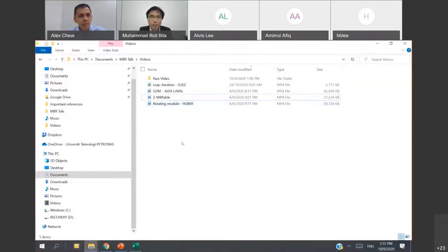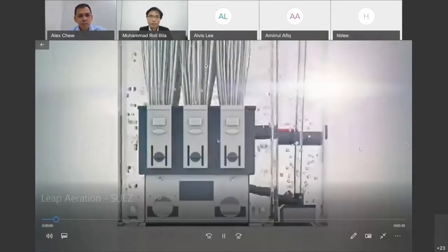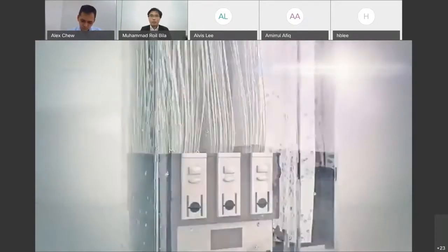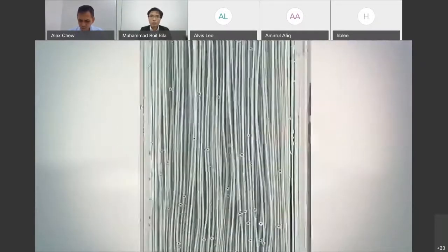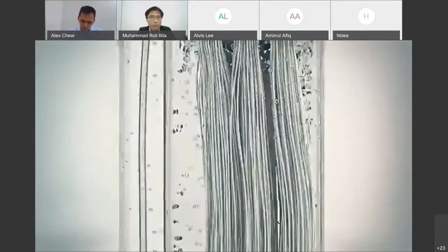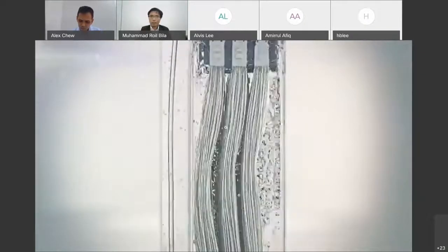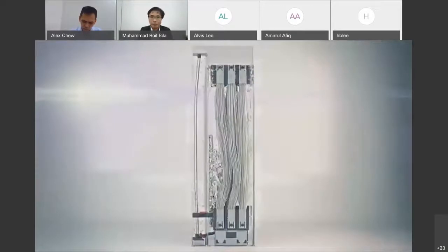For example, the first one is called LEAP MBR. This technology is commercialized by Suez. They use what they call slug flow to enhance the cleaning of the membrane. As such, it reduces the energy consumption significantly. So you see here that the air bubbles go intermittently with a high flow, and then the membrane can sway to the left and right, vibrating along the process.